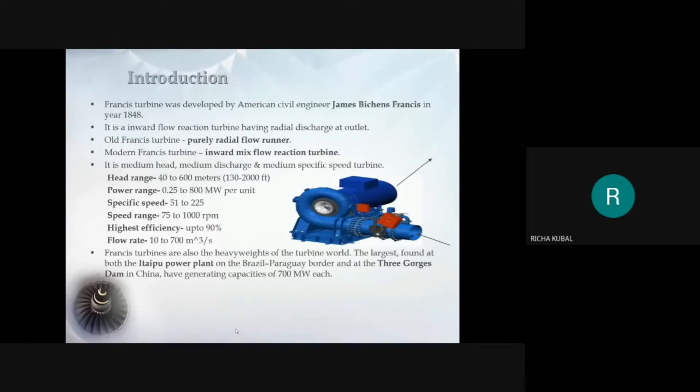This turbine is used where there is a need of medium head, medium discharge and medium specific speed. The head range is between 40 to 600 meters but delivers its best performance between 100 to 300 meters. The following are the other specifications of turbine as power range, speed range, specific speed, efficiency and flow rate.